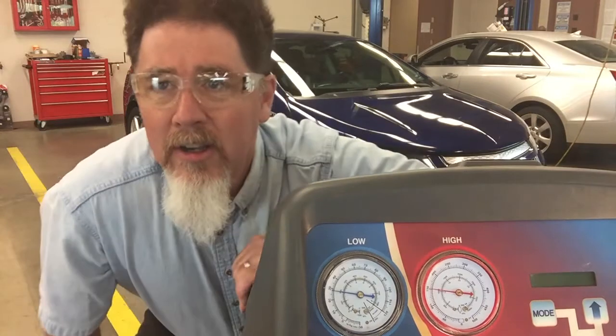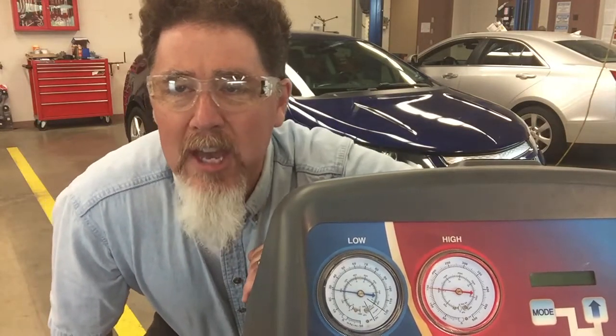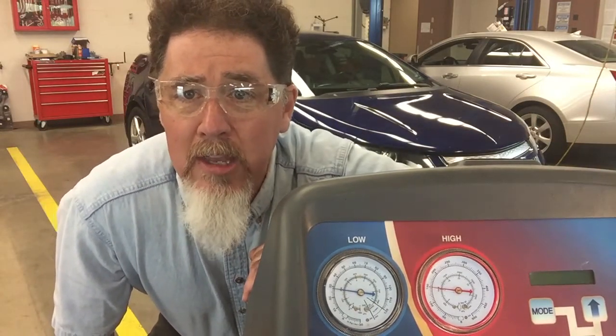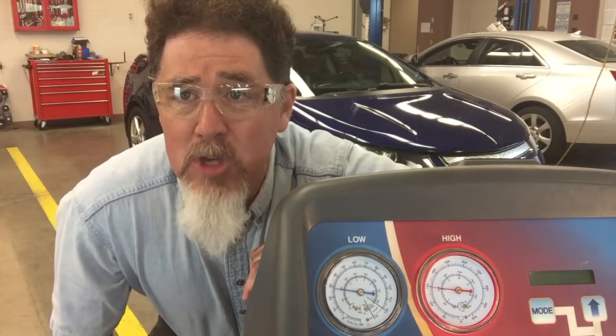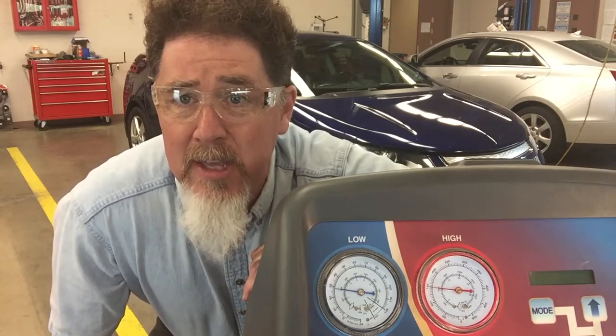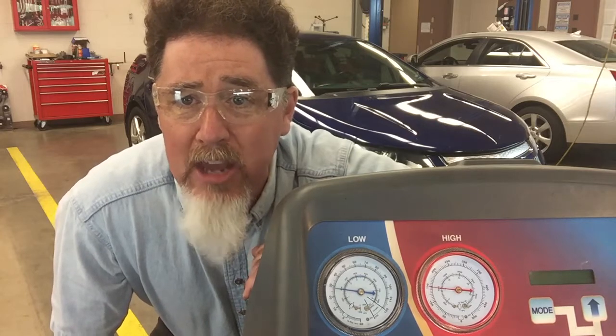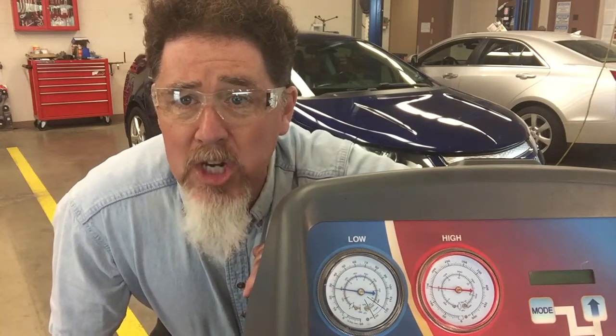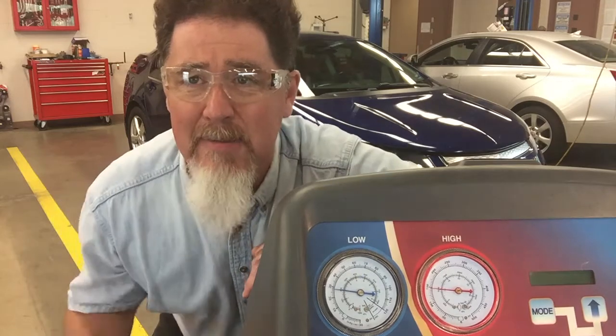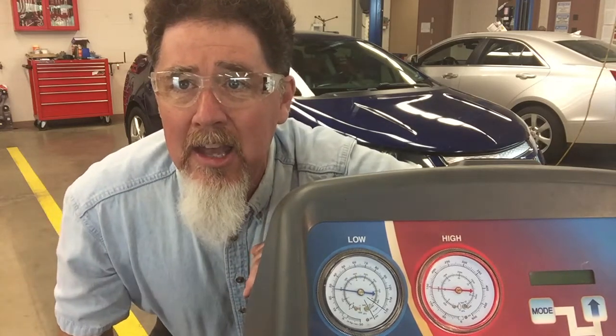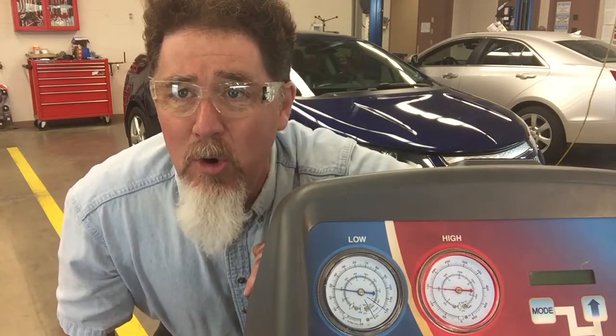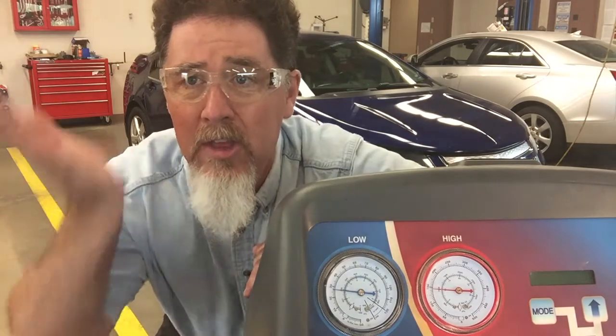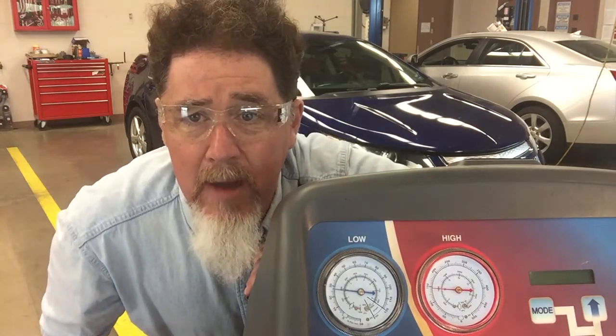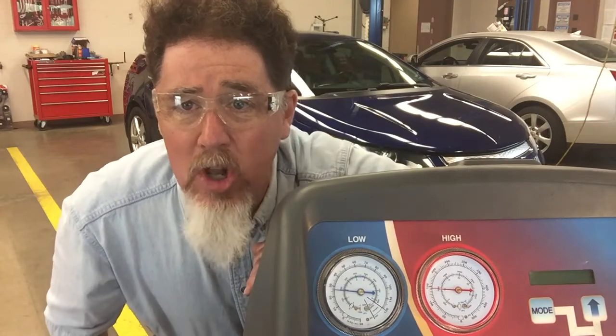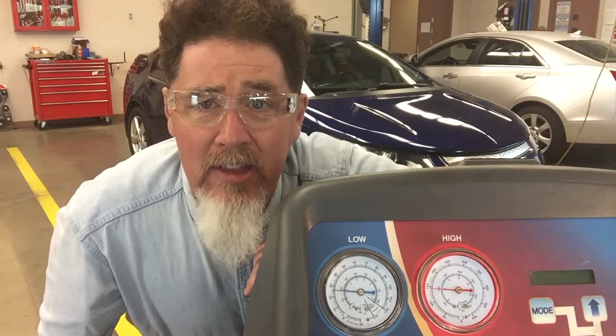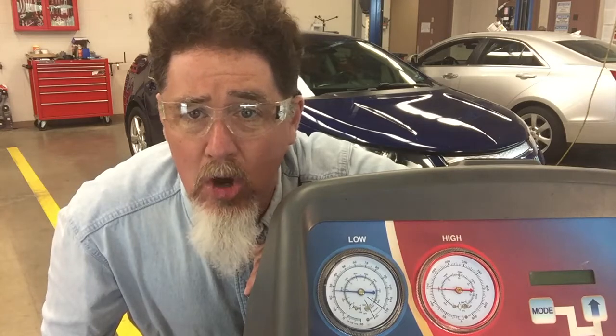So the rear AC unit is now turned back off again, so now only the front system is working. The front AC system is an orifice tube system, but the rear AC system is a TXV system. And so you can see by looking at the gauge readings, the low side pressure is starting to drop back down again because the system is not absorbing as much heat. And so heat equals pressure, and the more heat that's absorbed, the higher the actual pressure will be. So you can see the pressure on the low side is dropping down closer to 25, and then the high side is now dropping below 150.